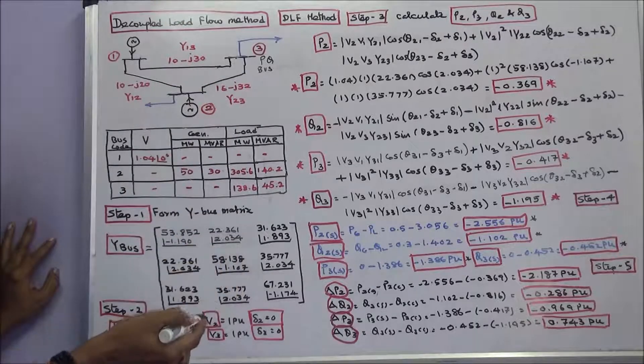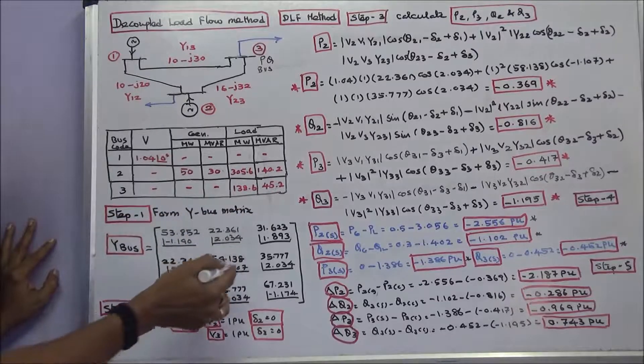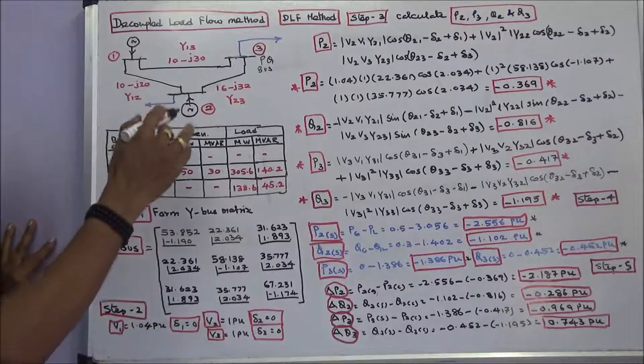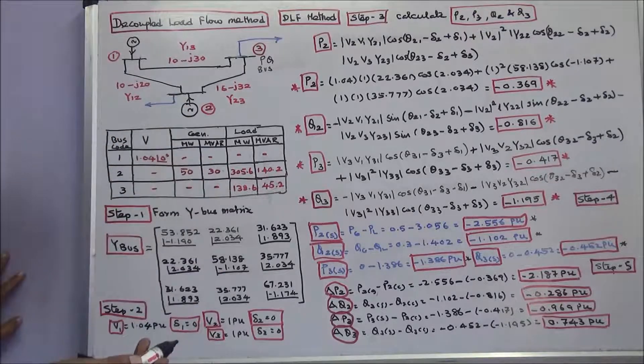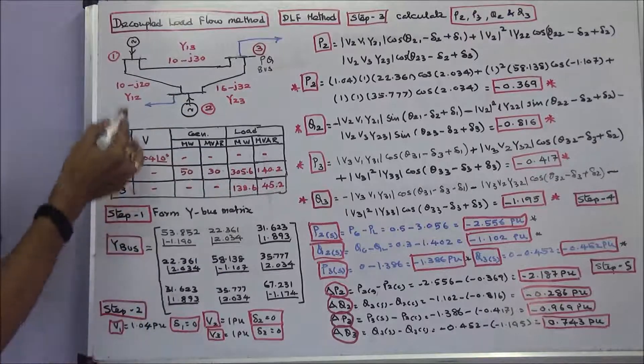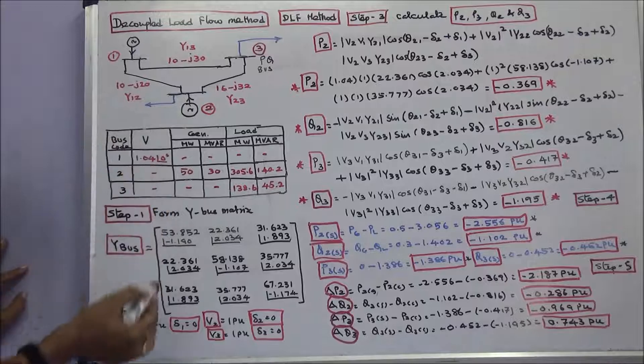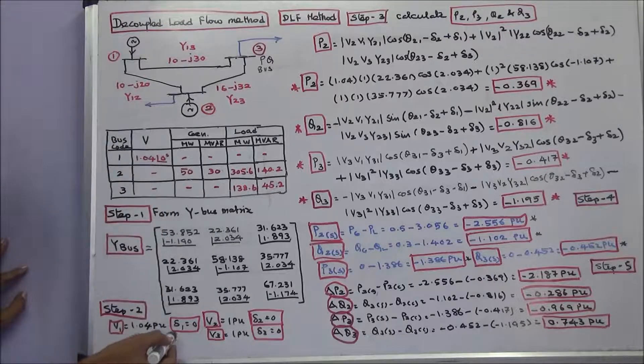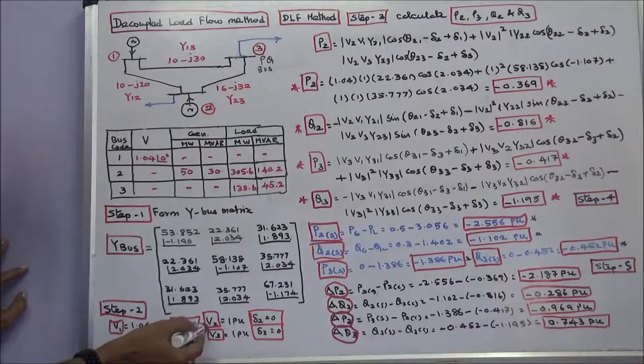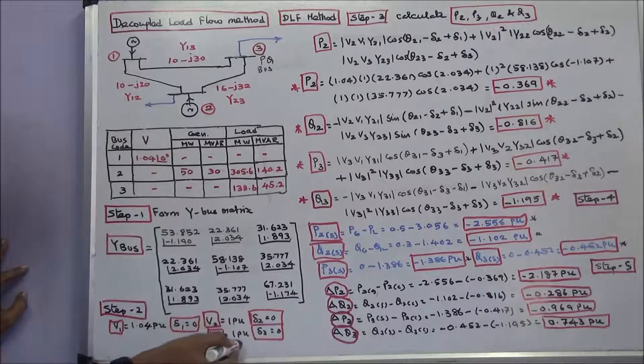Set the calculator in radian mode. Step 1: Form the Y-bus matrix. This is the Y-bus matrix of the system. Step 2: Initialize the bus voltages. The slack bus voltage is given as 1.04 at delta 1 = 0. For V2 and V3, we assume: V2 = 1 per unit, delta 2 = 0; V3 = 1 per unit, delta 3 = 0.